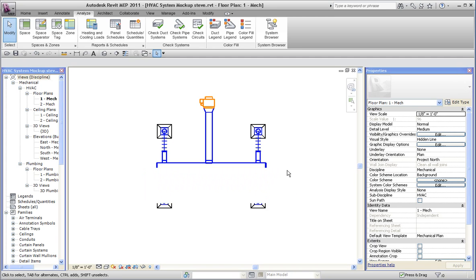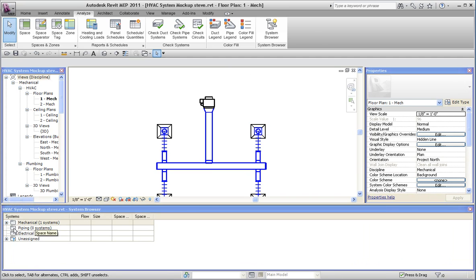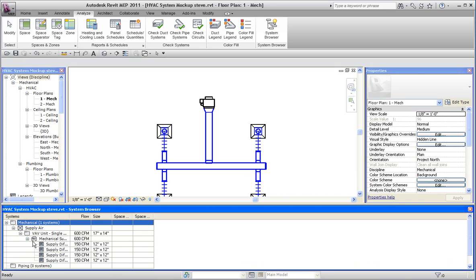So if I go in, try to do sizing, take a look at the system browser here, it's pushing the values properly up into the VAV and I don't get that duct warning error anymore.